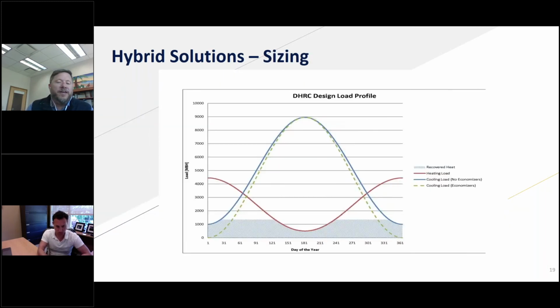So if we look at that as just a generic load profile, and I'm not even saying that this is representative of lots of buildings, but I've got something that shows this. The red line shows what the heating load is. The blue line shows what the cooling load is. And so in this example, as we step through this, the shaded area underneath is that year-round simultaneous load.